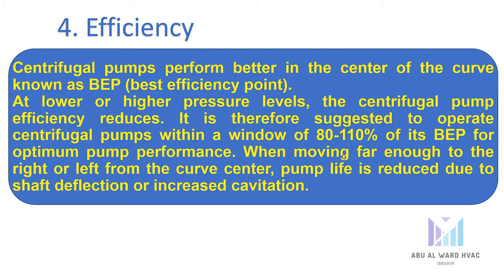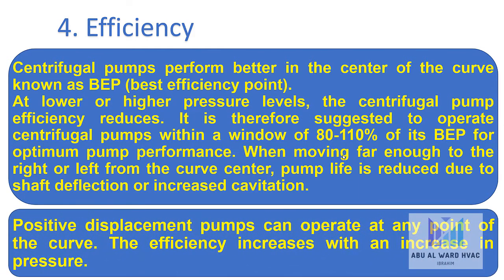The fourth aspect is efficiency. Centrifugal pumps perform best at the center of the curve, known as the Best Efficiency Point (BEP). At lower or higher pressure levels, centrifugal pump efficiency reduces. It is suggested to operate centrifugal pumps within 80 to 110 percent of BEP for optimum performance. Moving far from the curve center reduces pump life due to shaft deflection or increased cavitation. Positive displacement pumps can operate at any point of the curve, and efficiency increases with an increase in pressure.